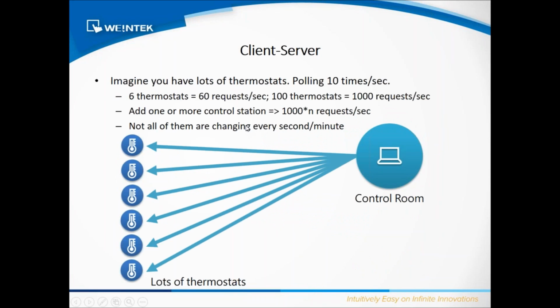The problem is if you have many thermostats and you're polling 10 times per second - with 6 thermostats that's 60 requests per second, and with 100 thermostats that's 1,000 requests per second. This is the problem of client-server architecture: the control room has to connect to every device and poll for information every second. And if another engineer also wants the information, it multiplies further.